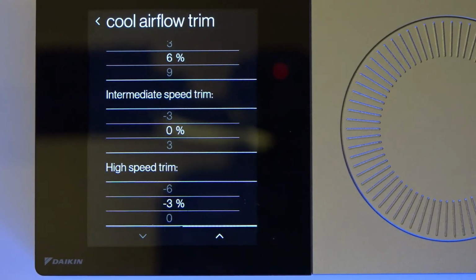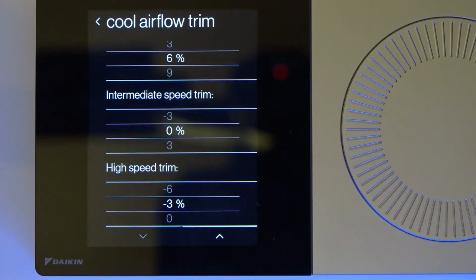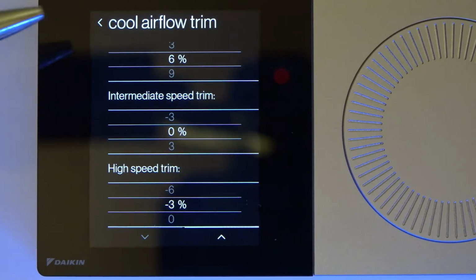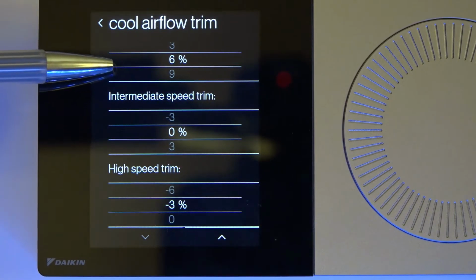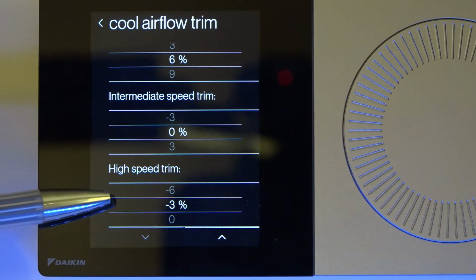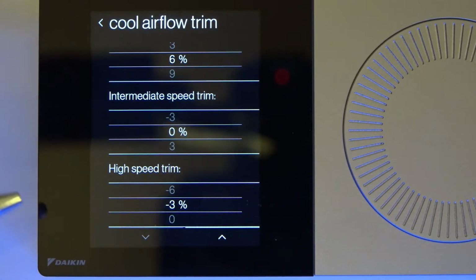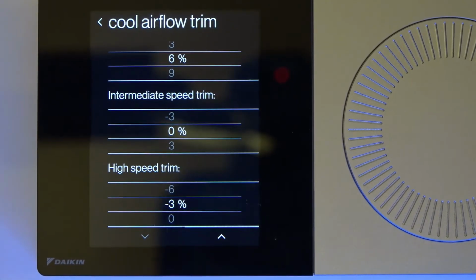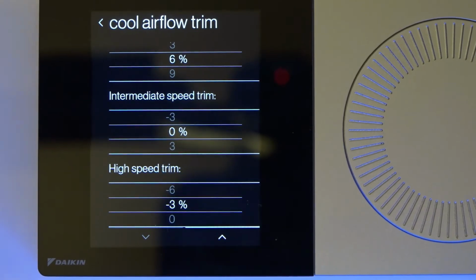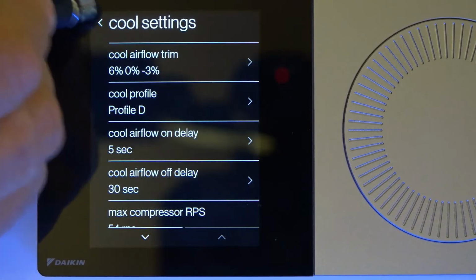Total system static is 0.5, so I need to stay underneath that. But that also allows the coil to be able to drain, and I don't blow moisture or suck moisture off of the evaporator coil and put it back into the airstream. I find here in the southeast that boosting it in the low range, 5 to 6%, and then in the high range, cutting it 3 to 5% does an excellent job for controlling humidity.